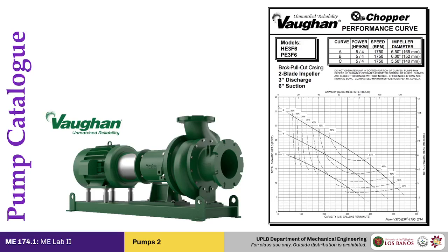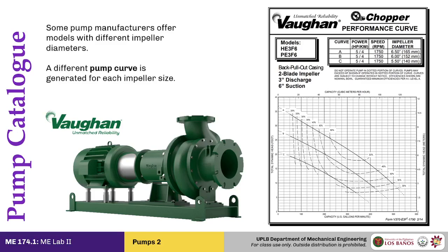So this catalog actually supplies pumps in different impeller sizes. It's just like the previous curve wherein you have these descending slopes, and each descending slope has an identifying letter identifying the impeller diameter. And you also have lines of constant efficiency.